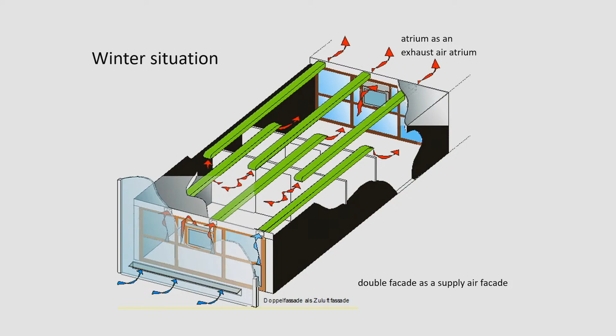What if we have ducts embedded in the concrete slab, connecting the office facing the atria to the double facade space, and connecting the space facing the double facade towards the atria. In the atria we have a chimney effect, and in winter the air in the atria is warmer than outside and wants to go out. So we get a chimney effect in the atria which pulls air through those ducts, from the double facade through the building. So despite the partition walls, we can have natural ventilation in winter.